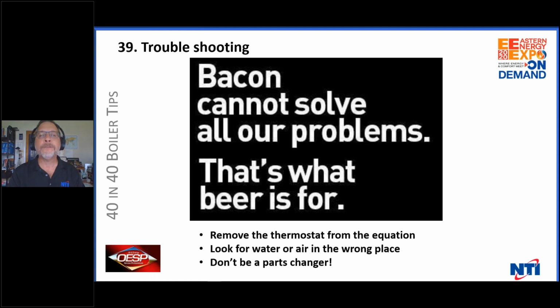Go upstairs. Don't even go upstairs. Disconnect the thermostat down at the boiler. Jump it out. I carry a toggle switch with 2 leads on it. I bypass the thermostat. Take it off. Put my own on. See if it works. Look for water or air in the wrong place. Yep. Air in the wrong place or water in the wrong place will do nasty things.